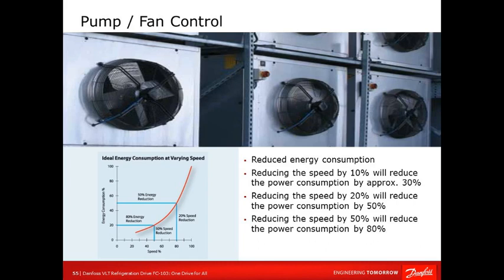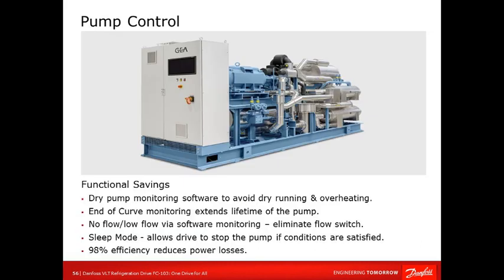And then for pump applications, again, some of the setup in the drive software can actually detect no flow or low flow. The drive could be programmed to either elicit a warning or alarm, or just alert the operator or the controller. So again, the idea is we're trying to improve the COP and improve the efficiency of the design of the system.